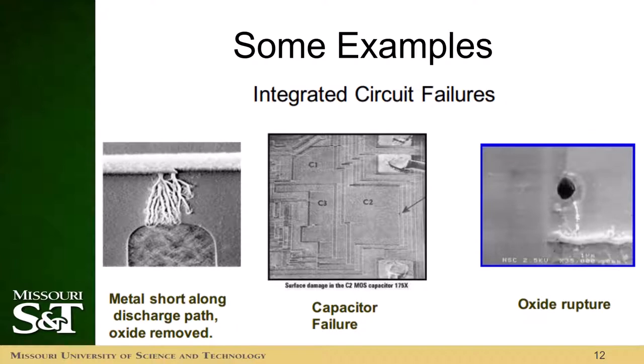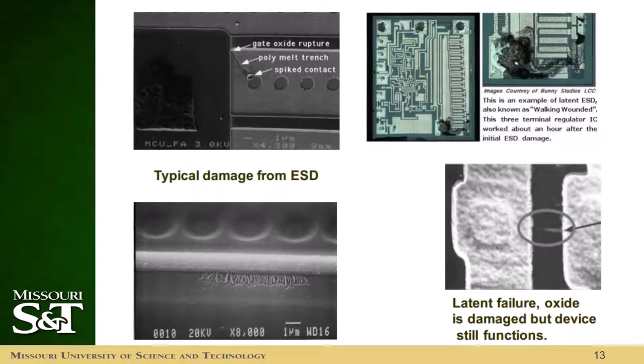Here are some examples of the damage types just discussed. On the left is an immediate failure — you can see it was just shorted from one component to another. The second image showing a capacitor failure illustrates how small this damage can be and how difficult it can be to detect. On the right is an oxide rupture. In the next slide, there's a bottom-right image showing a latent failure where you can see it starting to short from one component to another but not yet in contact. As the device is cycled on and off, that part will begin to degrade, and that short will eventually connect to the other component.